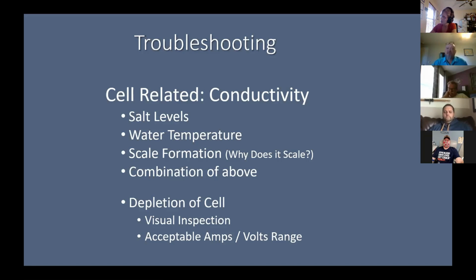Scale formation, why does it scale up? We talked about the saturation index, okay? A cell is going to scale up for one of two reasons. Under normal condition, everyone's system, we call it a self-cleaning cell, because what it does, it's a system of reverse polarity. The electrical polarity direction reverses direction about every hour and a half to 4 hours, depending on the manufacturer.